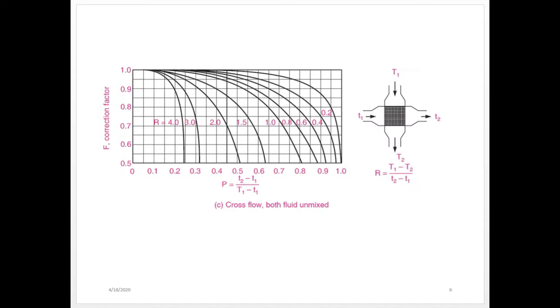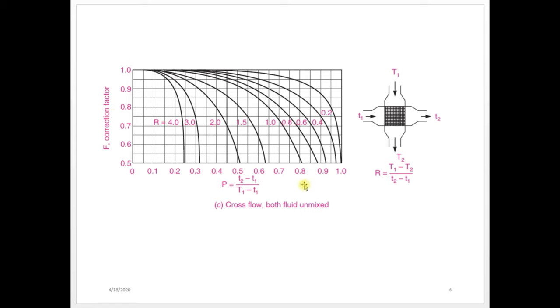Now we will see the third type, that is cross flow with both fluids unmixed. Cross flow means two fluids will flow perpendicular to each other. Correction factor F can be calculated with the help of R and P values. X-axis is P value, y-axis is correction factor F value, and these curves are R values. Based on R and P value, you can find out this correction factor.